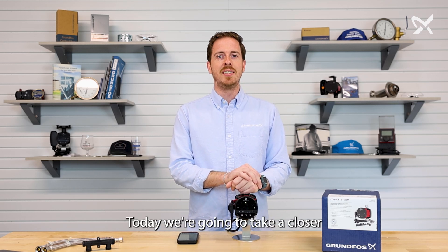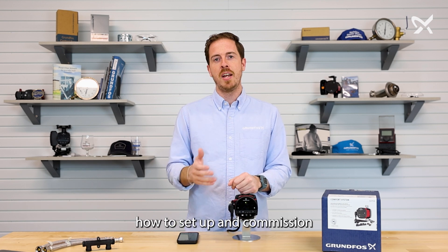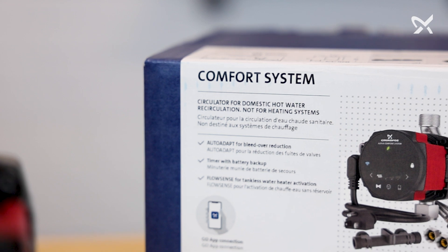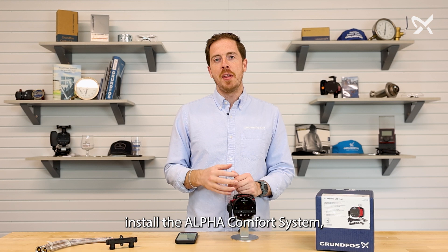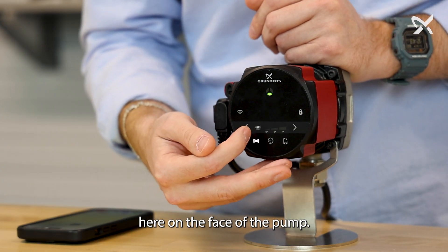Hey everyone, Ty from Grundfos, and today we're going to take a closer look at the Alpha Comfort System. We're going to show you how to set up and commission the pump. When you first install the Alpha Comfort System, the default setting will be auto-adapt, which you can see here on the face of the pump.